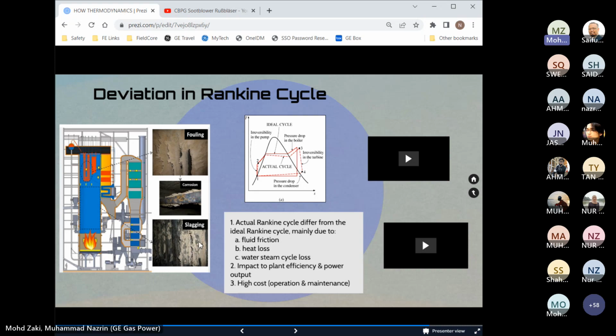For example, this superheater tube for the coal plant, we can see slagging and fouling. This will affect the heat transfer when we fire inside this boiler. Inside the tube we have water, from the saturated liquid, and we want to transfer the heat from the combustion into the tube. This will be affected because of the slagging, and that's why we cannot achieve the temperature that we want.